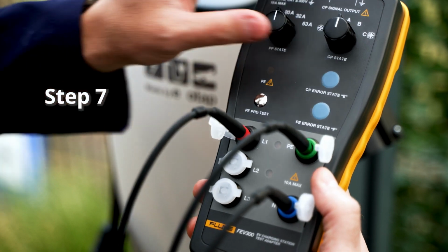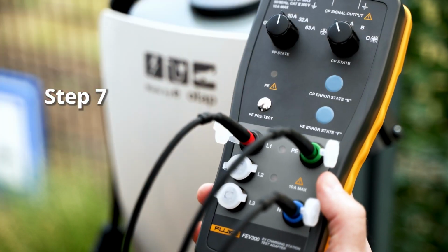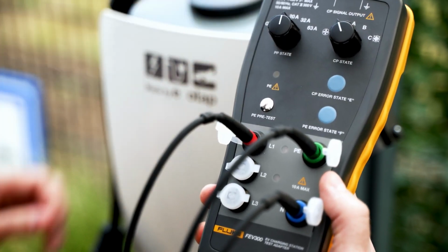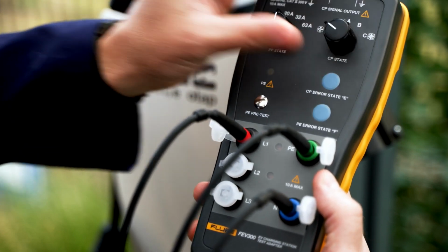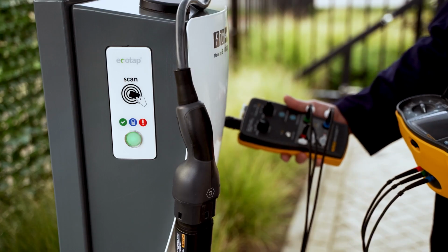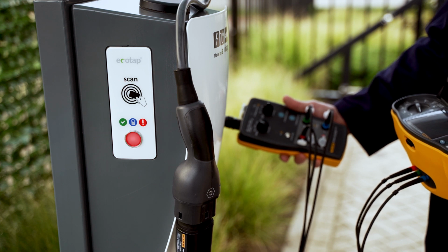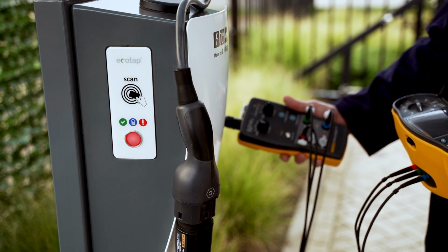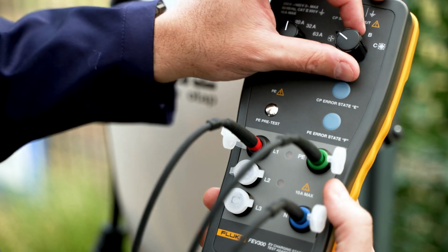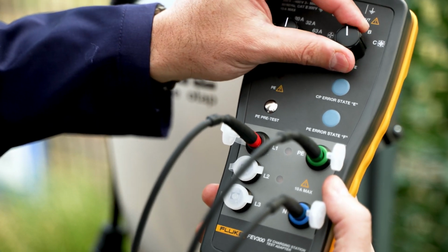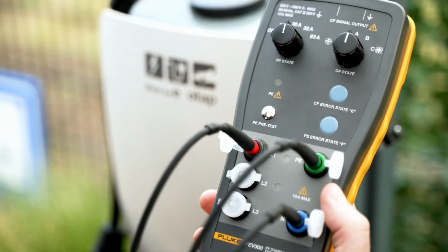Lastly, test condition D, charging with ventilation. Rotate the dial to status A, then B, ready to charge. Finally, select status D. As most charging stations do not provide charging with ventilation, the charging station should show error condition and the charging output should not be activated.